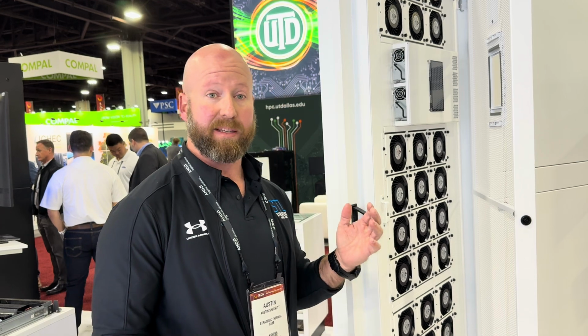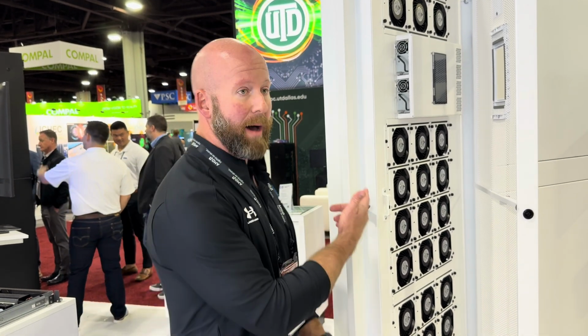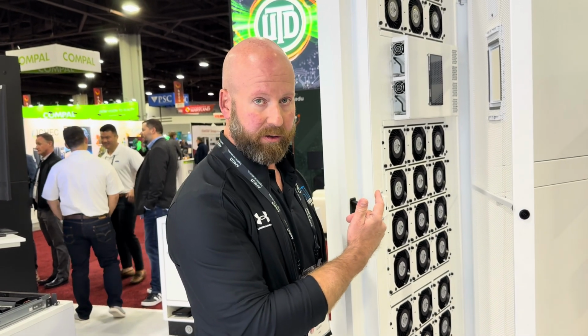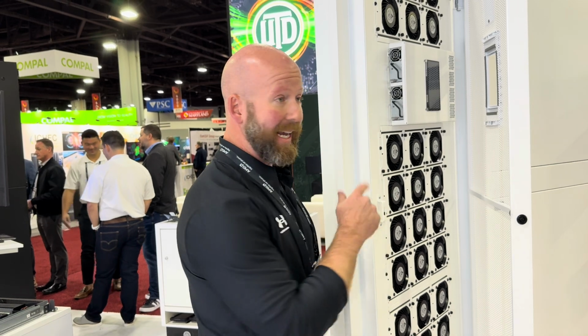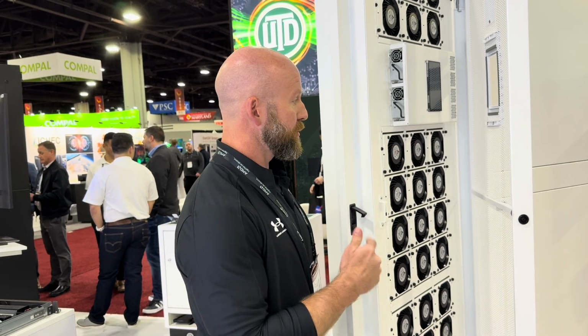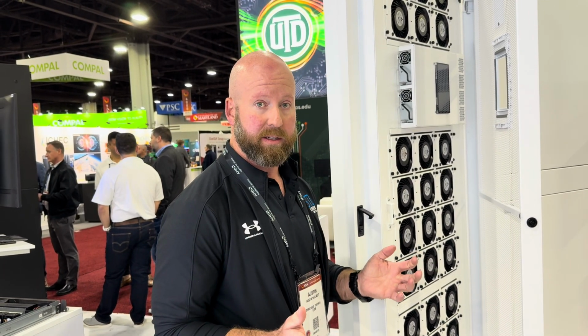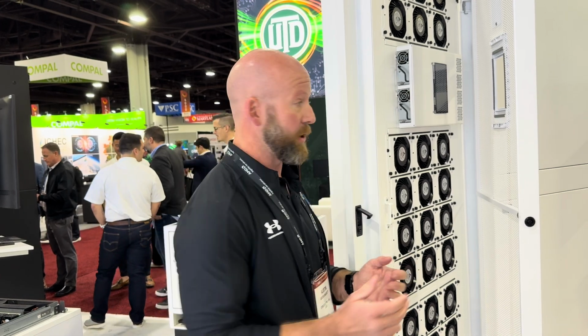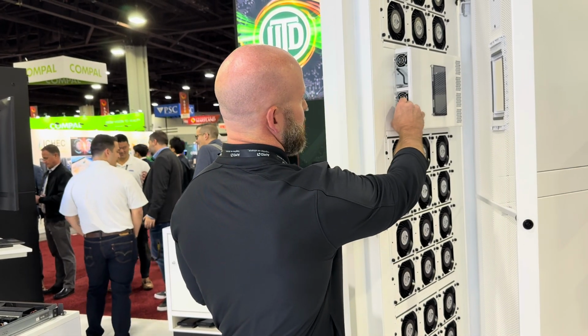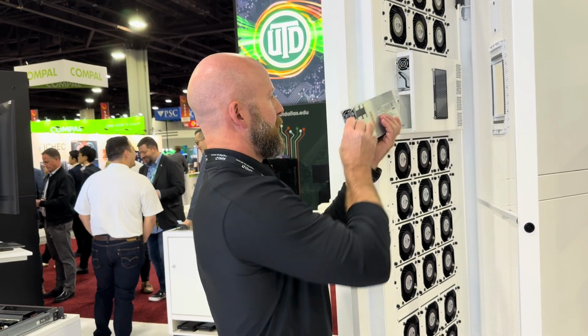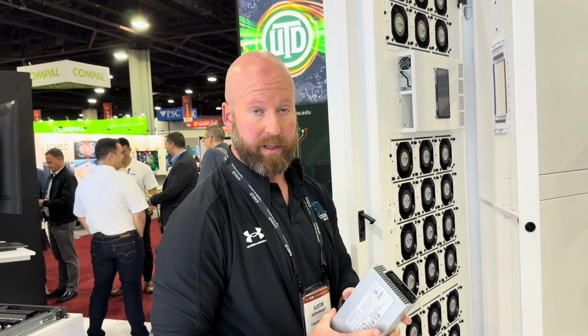Consequently, that has other nice benefits. One of them is that we can use commodity power supplies that are common in the server industries that give us AC to DC power conversion and also provide redundancy without requiring an automatic transfer switch. So all of our fans are powered off of the DC circuit, and our power supplies are commodity units that can be easily replaced.